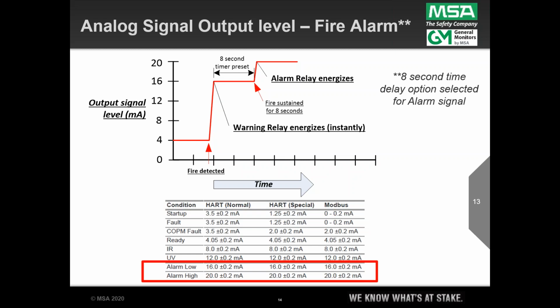Now, if we've got that 8-second time delay function set up like I mentioned, then as long as the energy being sensed by the device is sustained above that threshold for 8 seconds continuously, it'll continue off to the right until that 8-second timer is timed out. And boom, then the device output makes a step change to 20 milliamps, and reaching 20 milliamps correlates with the energizing of our sustained or timed alarm relay. At that point, the device has energized all its outputs other than trouble.